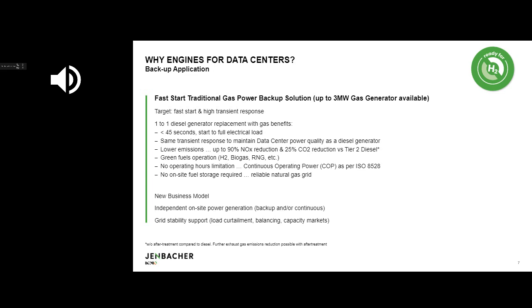Another important thing about these units, or the gas units themselves, versus traditional diesel applications or other technologies, is that these gas units, by definition and by ISO rating, have no operating hours limitation. So although we're talking here about backup applications, these units can really operate continuously - we're talking about 8,000 hours per year or so of continuous power. There's no limit. That's a massive advantage versus standard diesel, which by warranty and ISO definition typically uses the standby rating, limited to 200 to 500 hours per year of operation only.